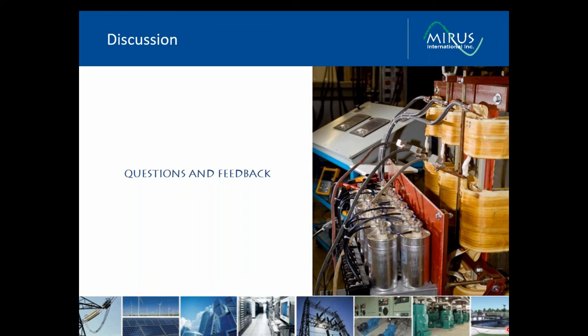There are certainly ways of doing computer analysis, computer simulation, to anticipate what levels of distortion you're going to get with your propulsion systems. SOLV is an excellent tool for doing that. At this point, it doesn't have active front-end drive models, and someday we'll probably introduce those as well, but you can certainly do your analysis with a standard six-pulse drive with line reactors or DC link chokes and with passive filters as possible harmonic mitigations. Definitely that's something that needs to be done beforehand, not after the fact.